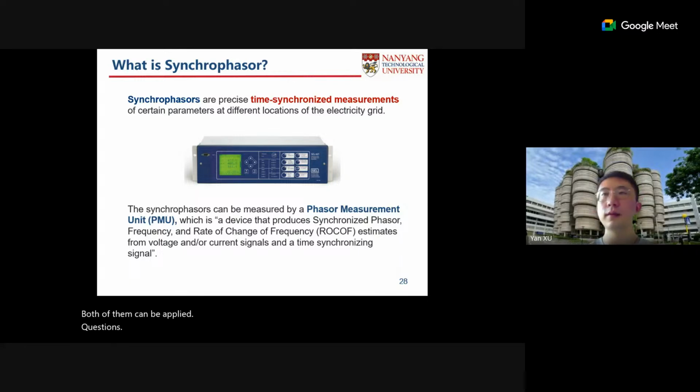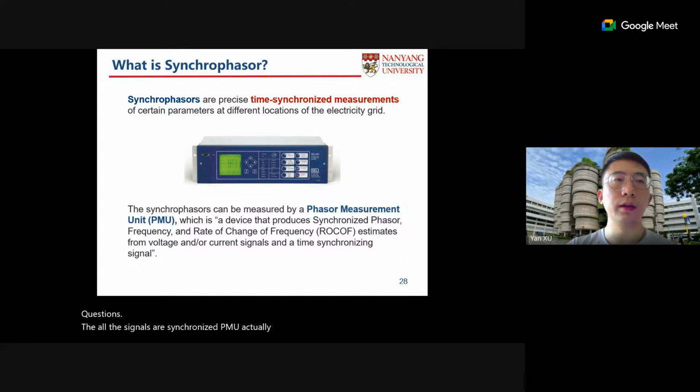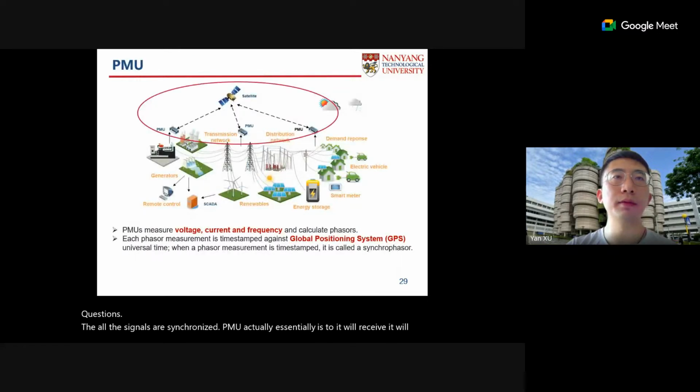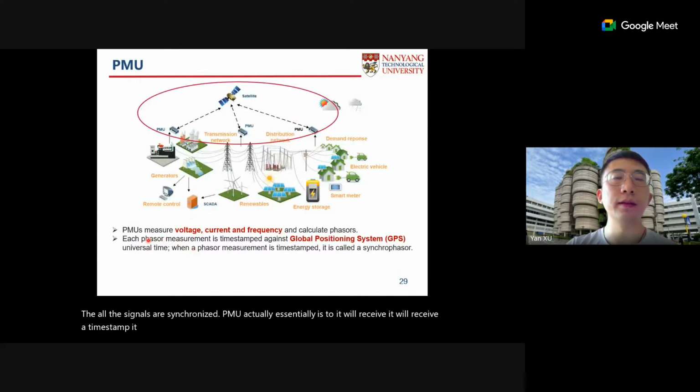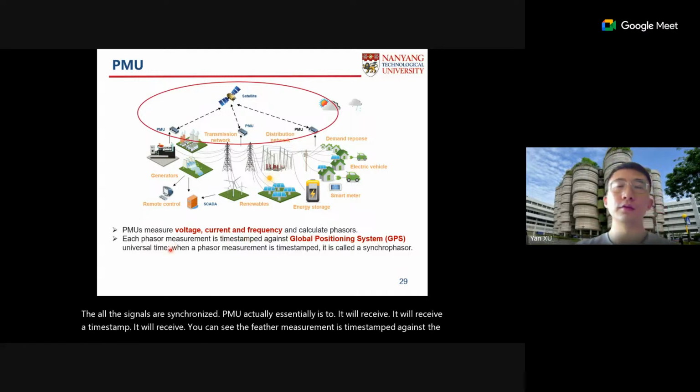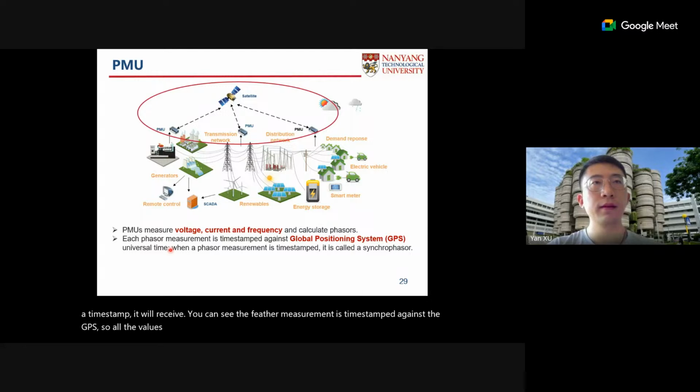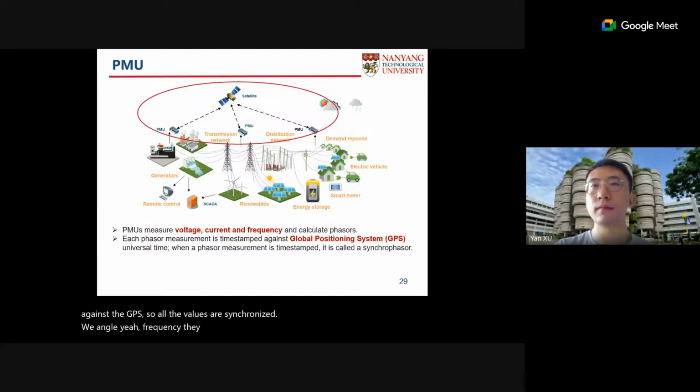Oh, all the signals are synchronized. You know, PMU essentially will receive a time stamp. You can see the phasor measurement is time stamped against the GPS. So all the values are synchronized. V, angle, frequency, they are all time synchronized.